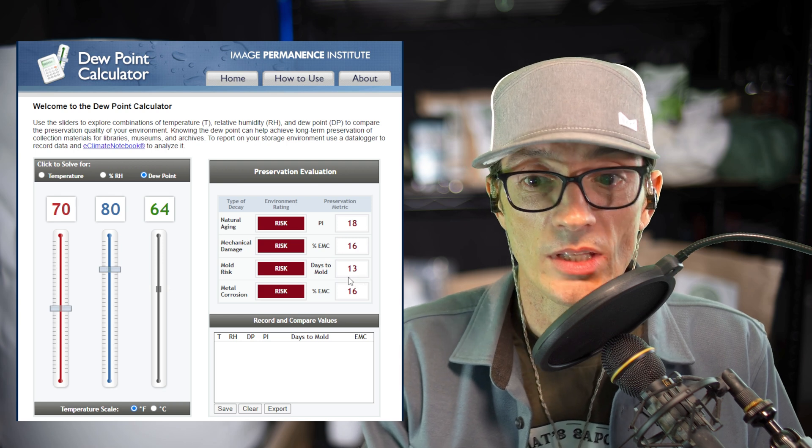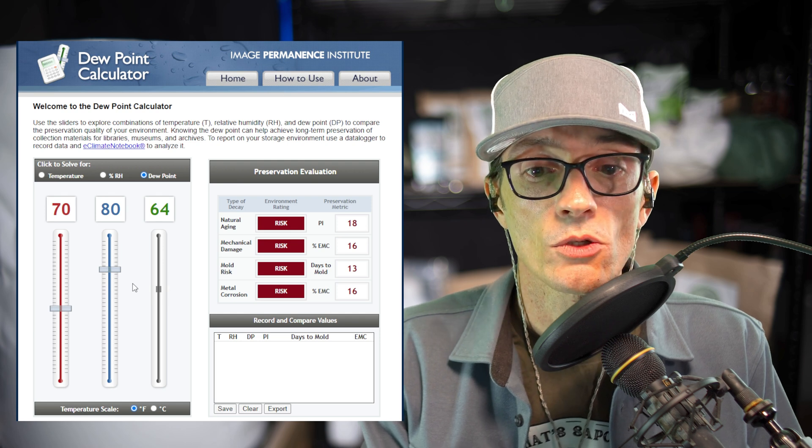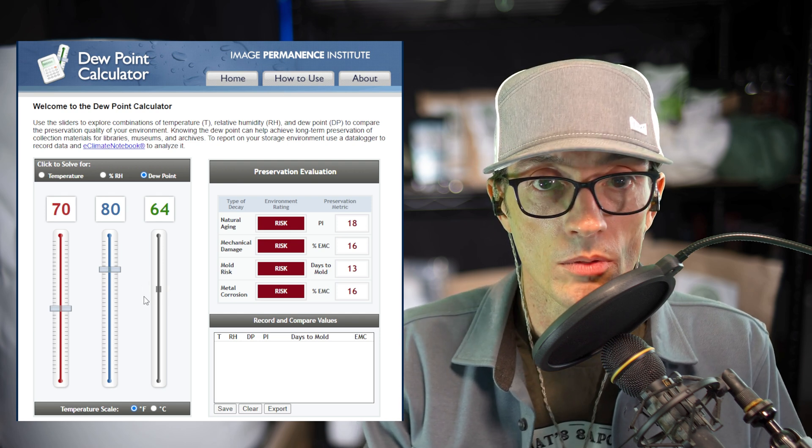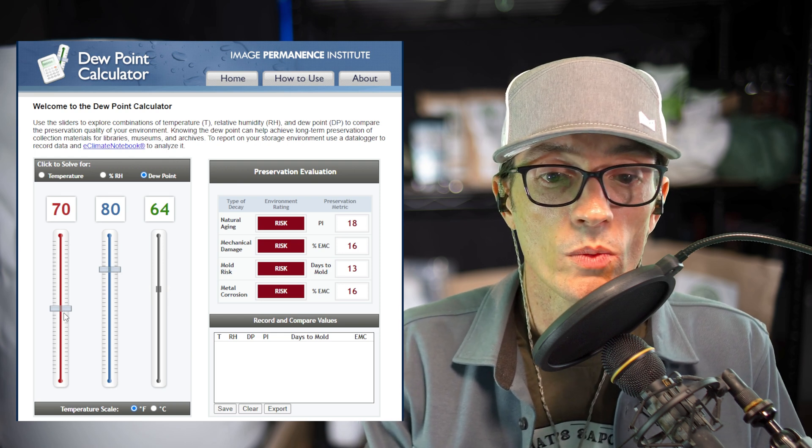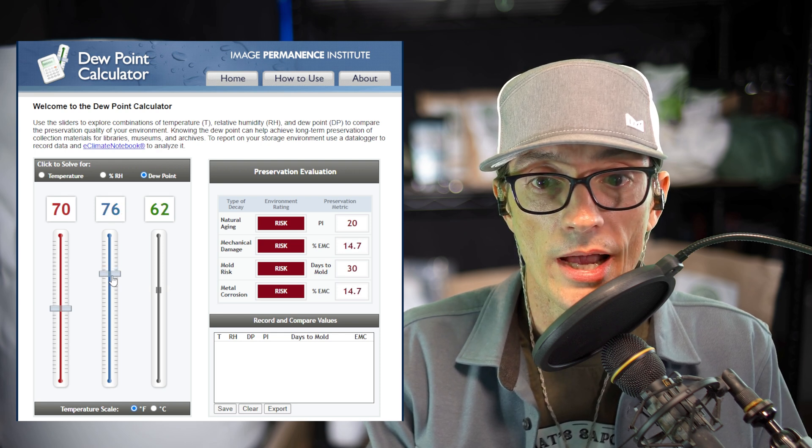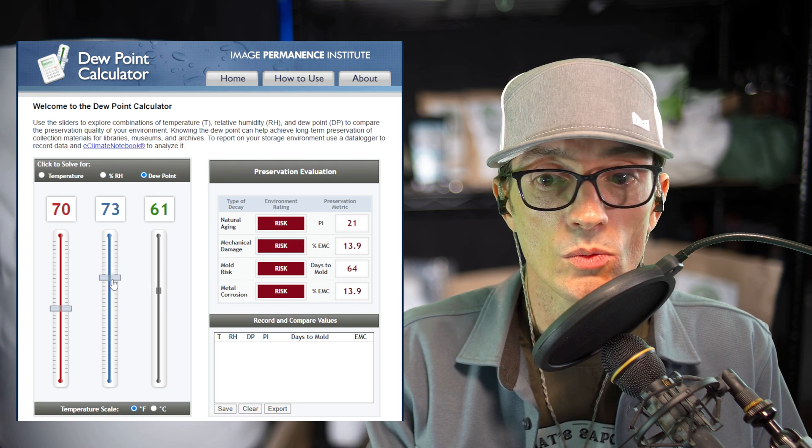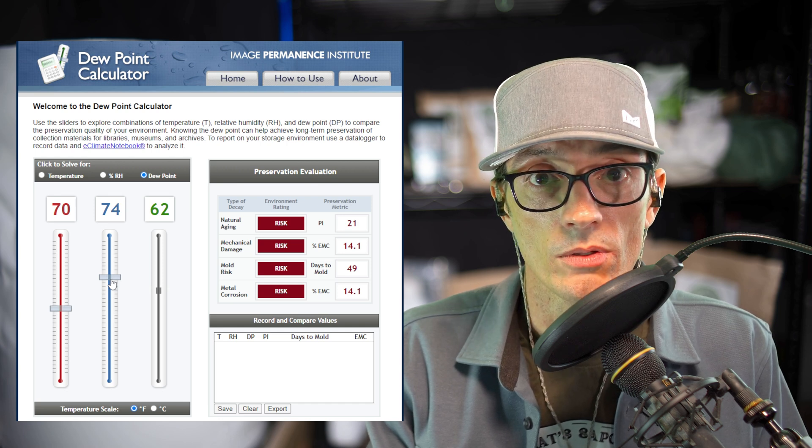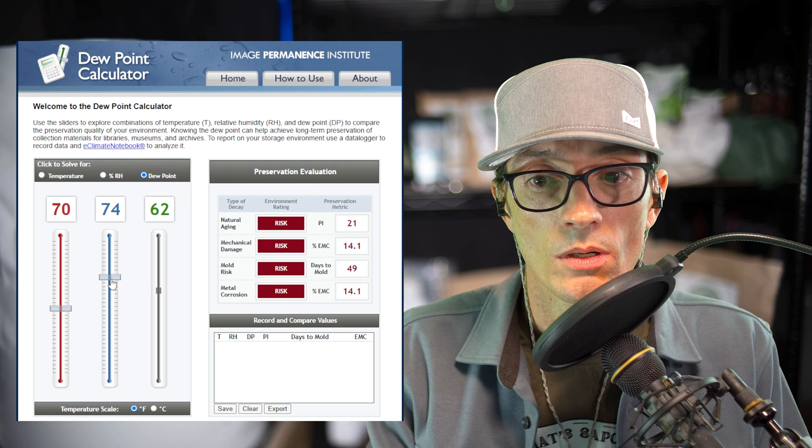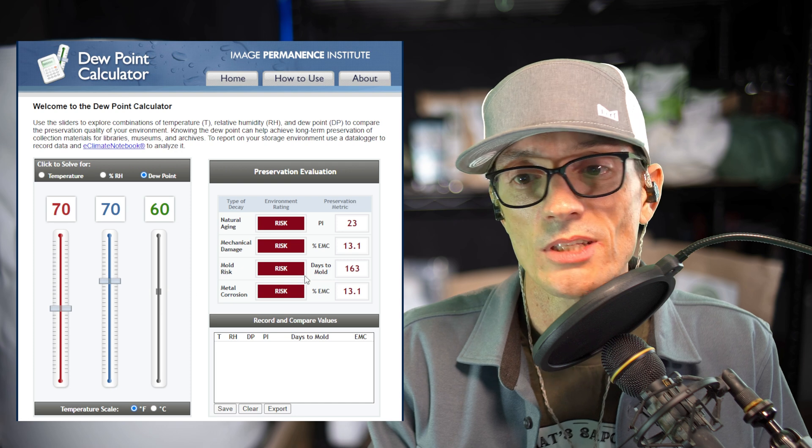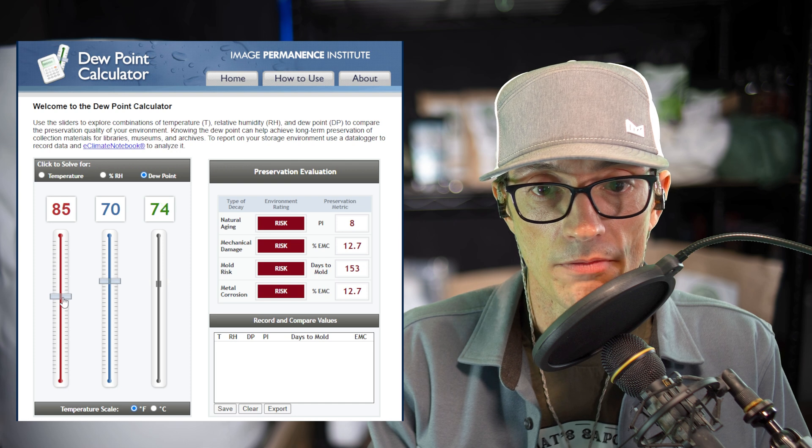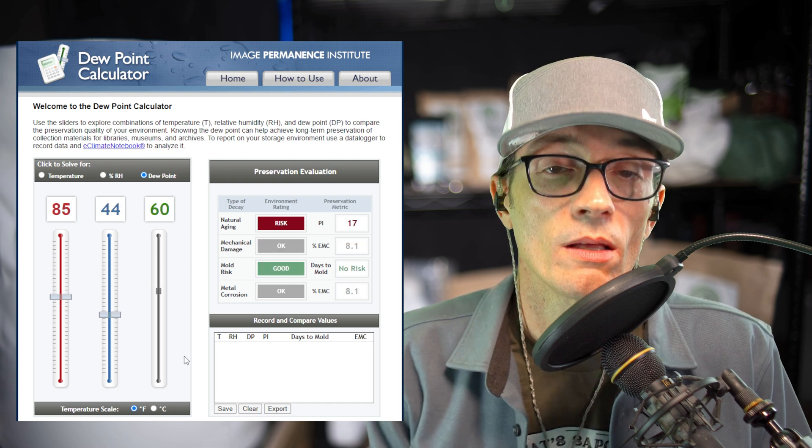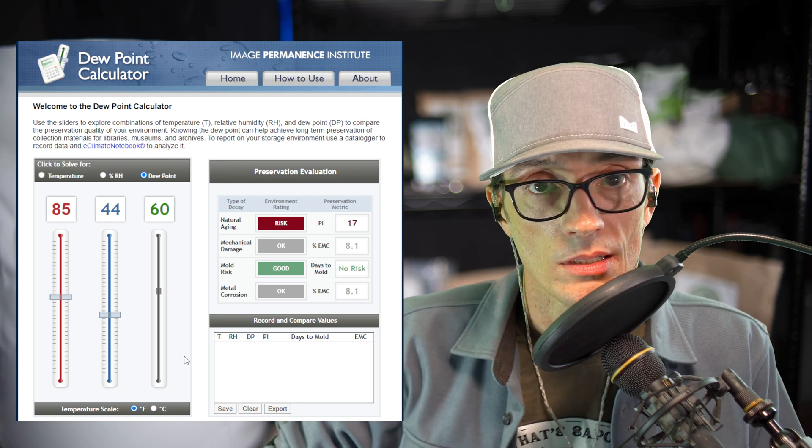This is not what you want. And if you were only monitoring the relative humidity, you would have not had the foresight to see this problem ahead of time. We already know we're at 70 degrees, so let's see where do we want to be when the lights go off. 30 days, we're still red, but now we're getting a little safer. 62, not a whole lot different of number, but if we bring that down to 62, we're a lot safer now. I would say maybe 60. Let's go down to 60. There we go, now we've got 163, we're golden. So let's see what 60 dew point would be at 85. Boom. 44% humidity is way lower than what you would think you would need in that situation.